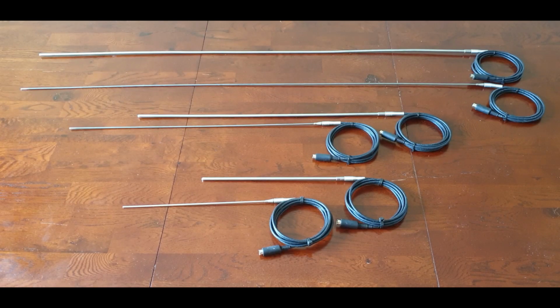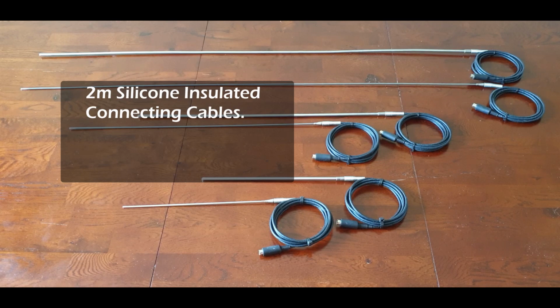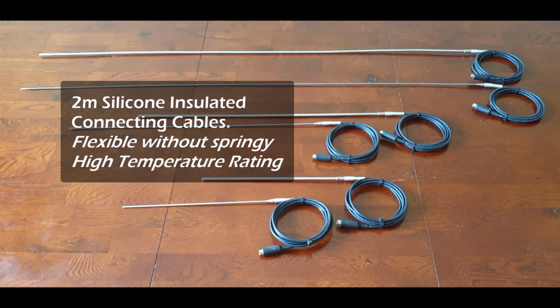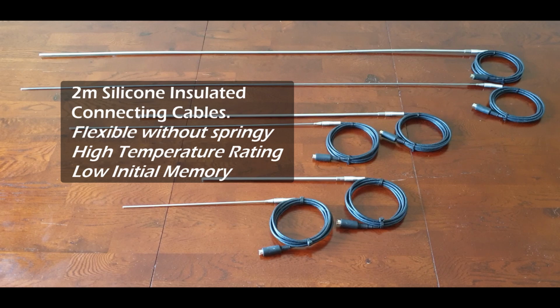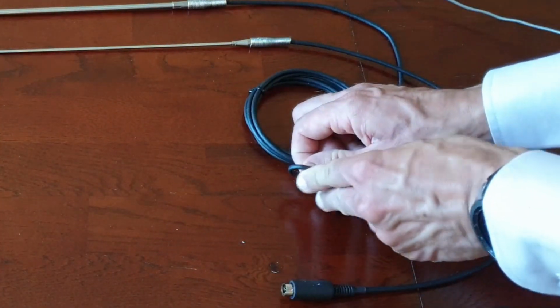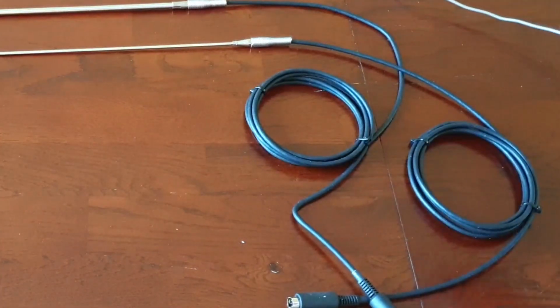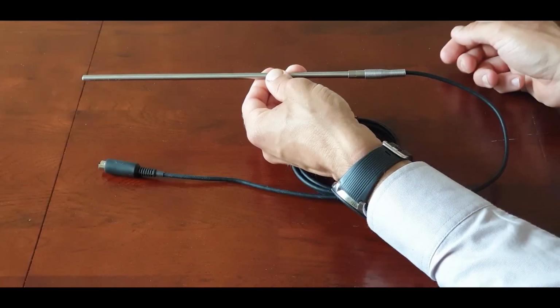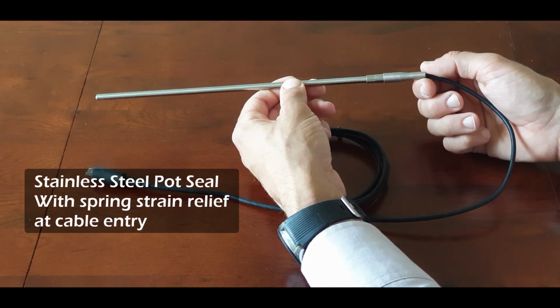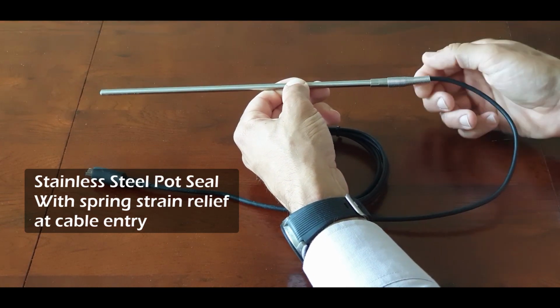Now they come in 2-meter silicone insulated connecting cables. Silicone cable is ideal for this type of probe as it is flexible without being springy and has a high temperature rating. Silicone cable has a low initial memory and therefore can be formed to shape and will stay in that position without pulling back to its original shape, unlike PTFE, PFA, FEP and to a lesser extent PVC. As an example, if I bend the cable like this, it will stay in position. The cable is terminated onto the probe and covered by a stainless steel pot seal with a spring strain relief at the cable entry.